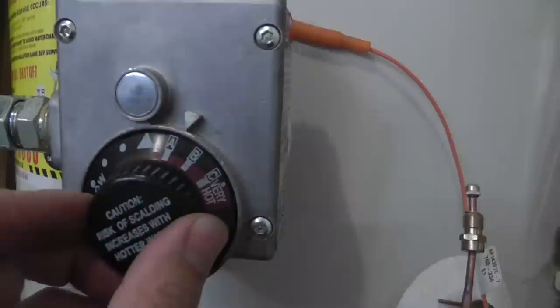From this pilot window, you don't see the pilot lights. Let's try to relight the pilot lights. Turn the temperature dial clockwise to the pilot lighting position. Turn the valve to the pilot position. Then press and hold the gas valve down and press the green little button to light.